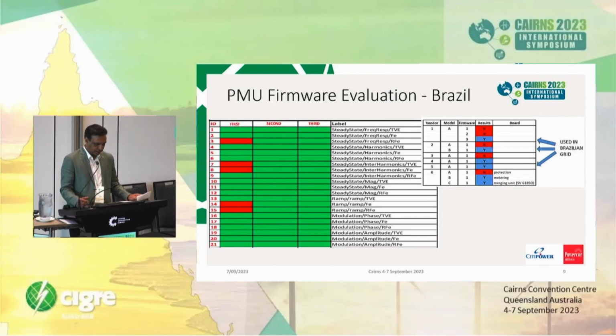On the right-hand column, you can see what sort of measurements were taken. Finally, their approval method is shown in the smaller table, where they have listed the vendor number, the particular model, mainly the hardware side of it, what firmware it had, and the results. You can see that vendor number 6 passed on the metering side, on metering with M class, did not pass on P with the firmware with hardware A, and then with hardware C, it passed even with sample values.